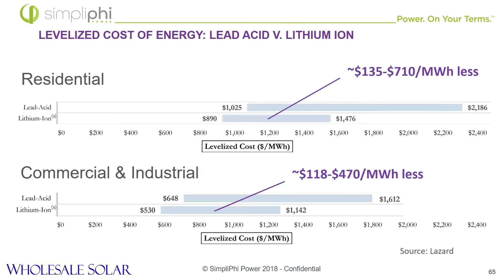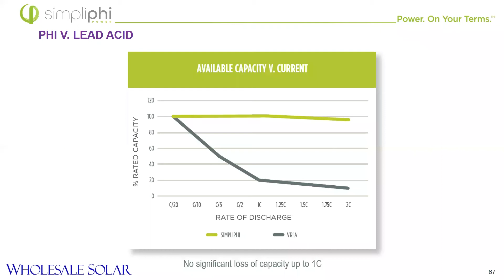So we're going to talk a little more about lead acid and show some graphs. Here you can see available capacity versus current, with rates of discharge at the bottom. It's okay if you don't understand what those mean right off the bat - we're going to get into that in a little bit. Generally speaking, you don't want to exceed a C/2 rate, but even if you did, the available capacity of our batteries is pretty uniform across all discharge rates.